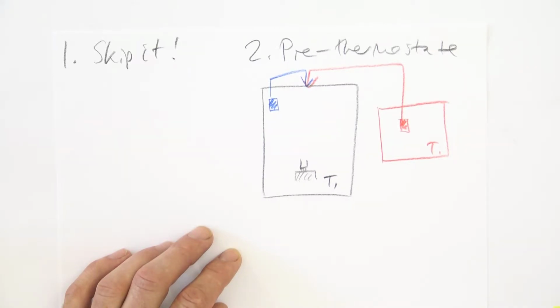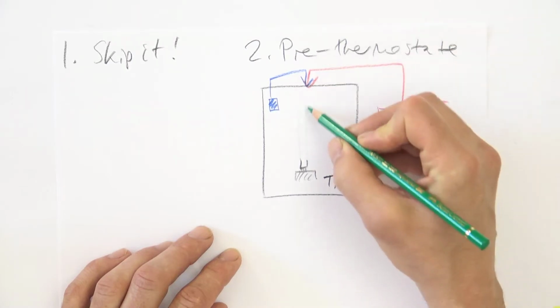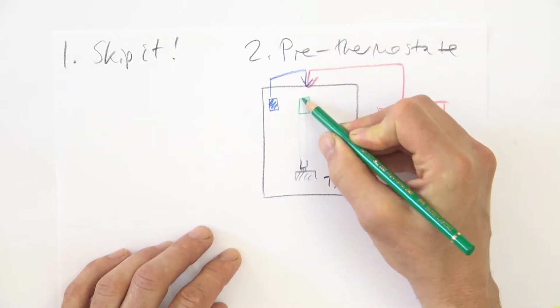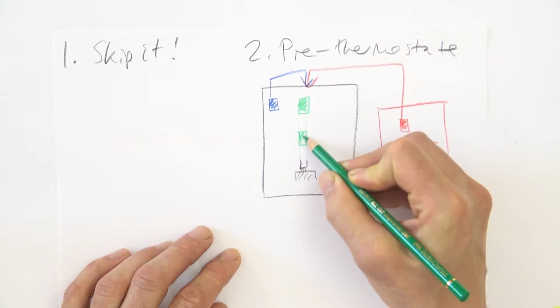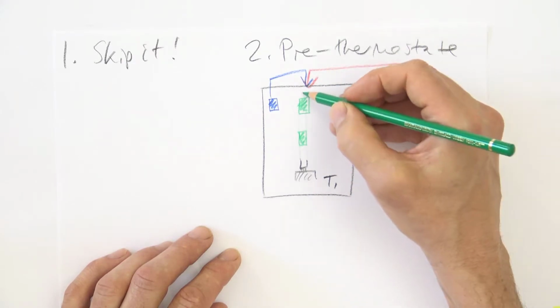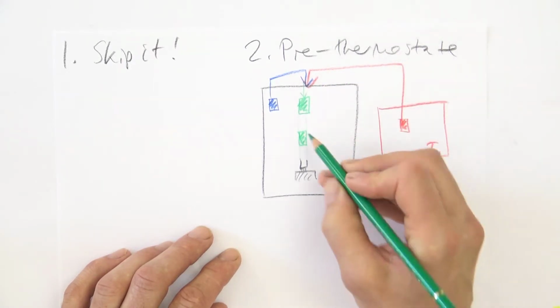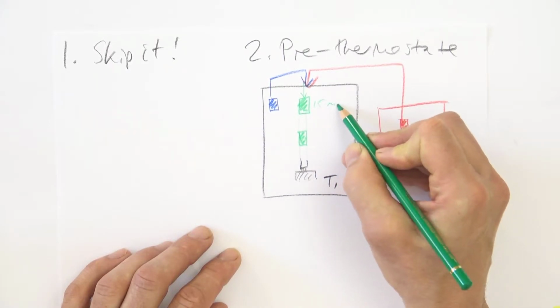And the third way is what is commonly done in microcalorimeters. That is to have 2 pre-thermostating steps or equilibration steps in the calorimeter. So you first charge your sample to a position in the thermostat and leave it there for, let's say, 15 minutes.